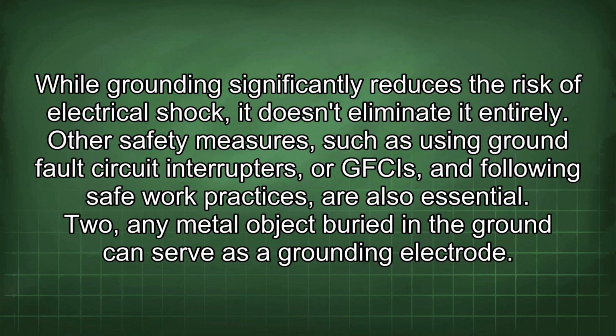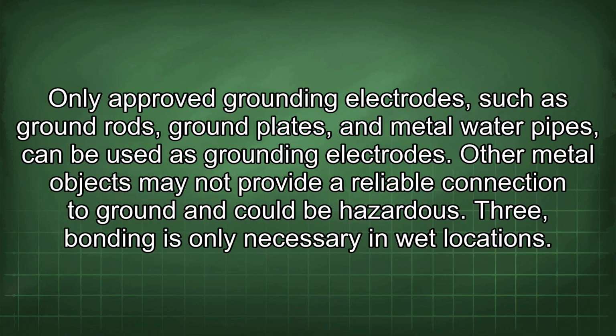2. Any metal object buried in the ground can serve as a grounding electrode. Only approved grounding electrodes, such as ground rods, ground plates, and metal water pipes, can be used as grounding electrodes. Other metal objects may not provide a reliable connection to ground and could be hazardous.